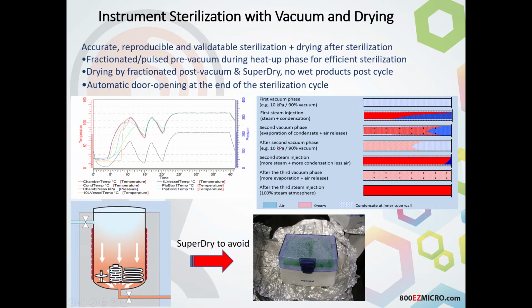We will also, inside of the system, measure the temperature and the pressure in this instrument all the way at the bottom where the air release is located. So during that pre-vacuum, we will be achieving different vacuum levels, and the unit will have to achieve those before it's able to pass on to the next segment of the cycle. So instead of just the autoclave reaching 121, we're reaching it at the exact point where physically it has to be 121 and the pressure has to be correct in order to verify that the entire vessel is full of steam.